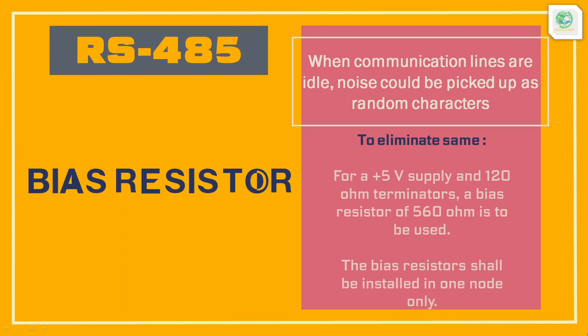During normal operation, there are some periods when all RS-485 drivers are off and the communication lines are in an idle state. In this condition, the lines may pick up noise, which will be interpreted as random characters on the communication line. To solve this problem, we should incorporate bias resistors. For a +5 volt supply and 120 ohm terminators, a bias resistor value of 560 ohm is sufficient. The bias resistors are to be installed on one node only.